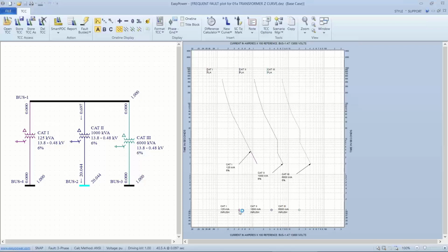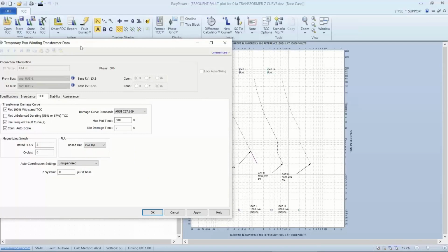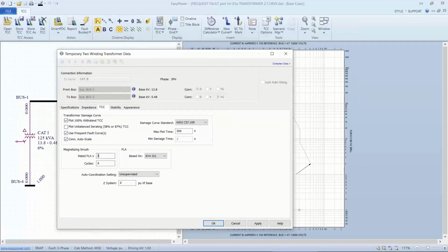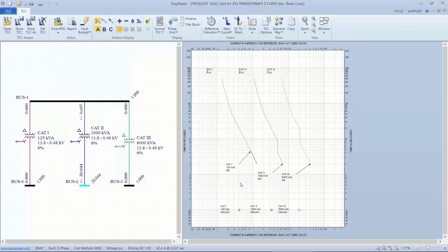Now we talked about the inrush, or rather haven't talked about it yet. Inrush is also based upon the parameters that we've input into the tool, and in this case, typical values are 8 to 10 times full load current and a 6 cycle time delay. So what this means is if we're going to have protective devices set up for the transformer, they don't want to be sensitive enough to be tripped by the current inrush when it's first energized. Now this applies only to primary protection, and I think I've got more information on that as we're going along.